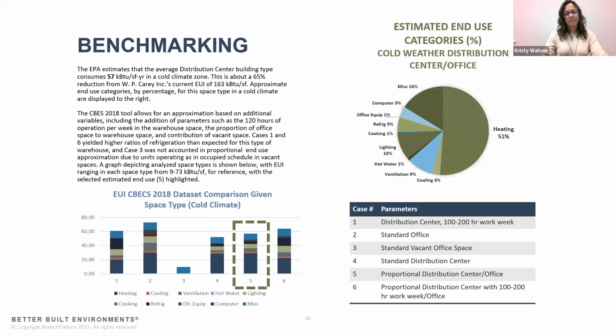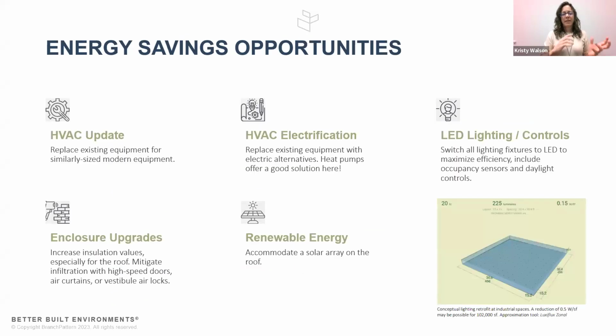Because we had the benefit of going on site with the energy audit, we were able to get eyes on the enclosure. When we sat down at the energy model to calibrate it based on utility bills, we could not get the model to use as much natural gas as the actual building was using. At the end of the day, we had to speculate that the enclosure had a lot to do with that, including potentially dock doors being left open throughout the day or at certain times.